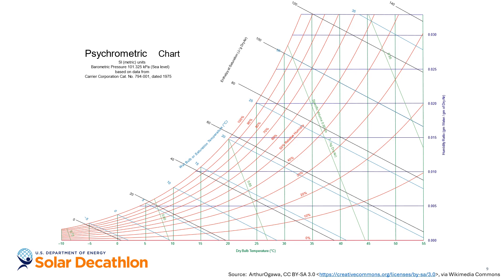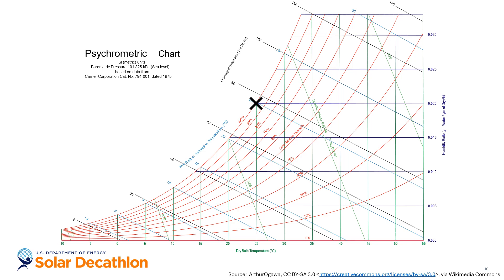One thing you might notice right away is that the chart seems to be missing the upper left portion — it's cut off on a curved edge. This edge is known as the saturation line. At a given temperature, air can only hold a certain amount of moisture before it becomes fully saturated and water vapor condenses into liquid water. If we look at a dry bulb temperature of 25°C and follow that line up to the saturation curve, we see the 25° dry bulb and wet bulb lines intersect at this point. Being at the saturation curve means the air cannot hold any more water vapor — it's holding 100% of what it possibly can. This is known as the relative humidity of the air, depicted by curved red lines.